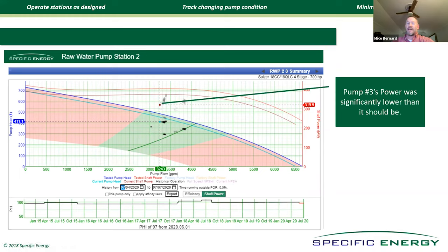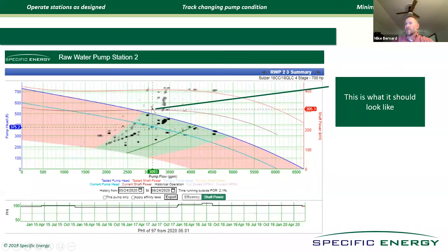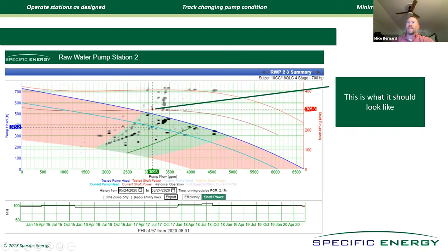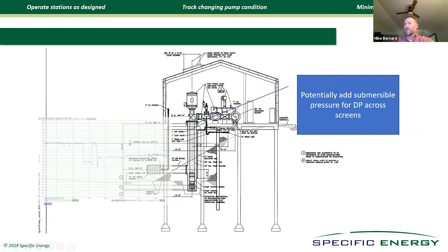Now, one of the new features that we added last year was this shaft power button. We did it to give us an indication of something was going wrong with the pump. In this case, we saw it on this day and Perry and I were talking about it. It could have been suction side plugging that was causing this dot to be below this line or it's a four stage pump—there was a slight possibility that they had spun off one of the stages from the pump and that's why it wasn't pulling as much power. We called Casey and said, hey, we're pretty sure pump number three is up. Could you go have somebody hit the back pulse button on the screen and let's see what happens. He's like, are you serious? It's 20 miles away. I said, well, if you don't, you're likely going to burn up this 700 horsepower pump. And so we sent somebody out there. As soon as they hit the button, this is what it's supposed to look like. The dot comes back onto the line. And now we have proof positive that we are able to predict suction side plugging on these pumps, which is hugely valuable.